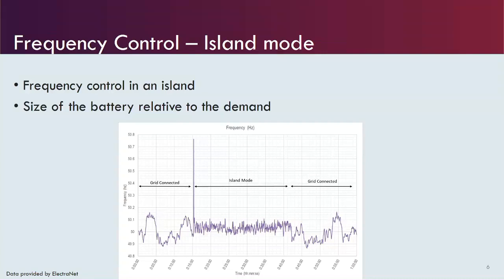Following a disconnection, the battery is actually pretty good at helping control frequency over this islanding period - we want to keep frequency in as tight a band as possible. Here it's not exceeding 50.1 hertz, which by Australian frequency control standards is good, though by international standards it's pretty bad. But we can see that prior to and after reconnection, frequency control is actually a little worse.